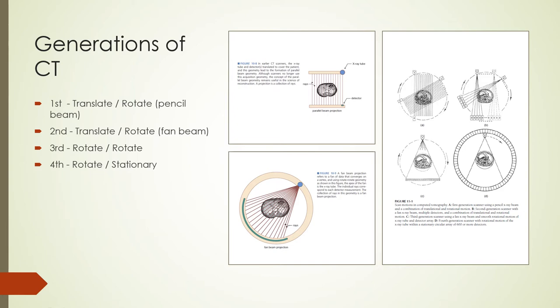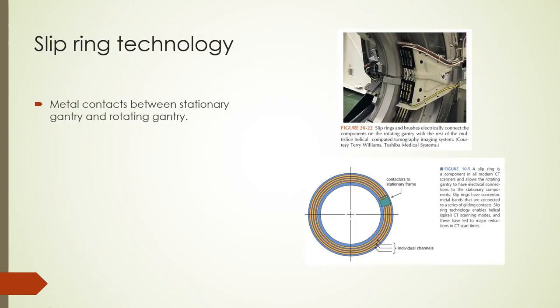In third-generation scanners, a curved detector rotates around the patient in synchrony with an X-ray tube in a rotate-rotate geometry — used by most modern CT scanners. A fourth-generation system has a circular ring of detectors in a fixed position with an X-ray tube rotating inside. Slip ring technology, which connects the rotating gantry to the stationary gantry without wires, enables this rotate-rotate geometry and helical scanning, leading to reduction in scan times.